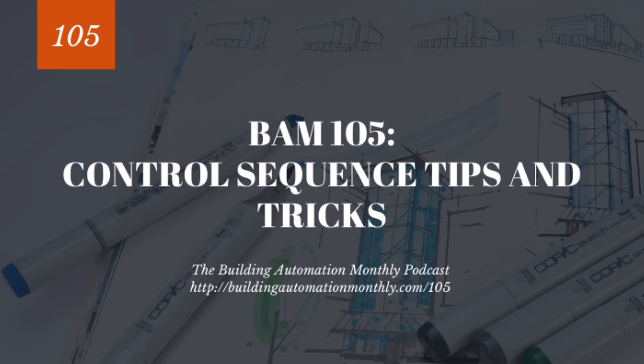If you don't have issues in the summer, and during the summer that box sits at like 20-30% when the rest of the boxes are at 60-70%, that's an indicator that your max flow setting is too high, which, if your max flow setting is too high, then usually your minimum flow setting is too high. And that's what the issue was. His flow settings were too high, and because of that, he was providing too much flow to the space. So I said I'd give you 3 scenarios, right?